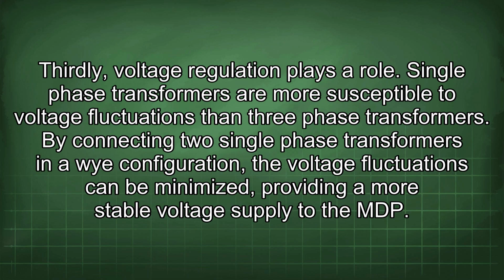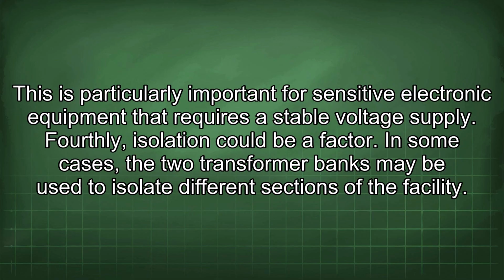Thirdly, voltage regulation plays a role. Single-phase transformers are more susceptible to voltage fluctuations than three-phase transformers. By connecting two single-phase transformers in a Y configuration, the voltage fluctuations can be minimized, providing a more stable voltage supply to the MDP. This is particularly important for sensitive electronic equipment that requires a stable voltage supply.